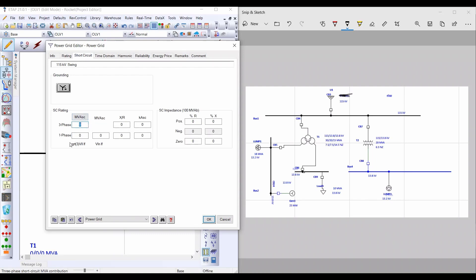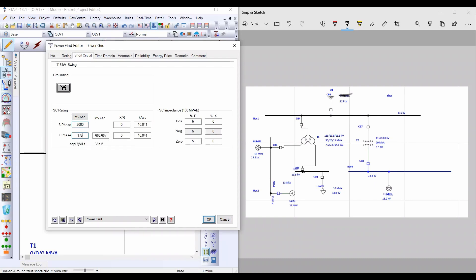Single-phase fault means line-to-ground fault. The value for three-phase fault is 2000 MVA short circuit, and for line-to-ground fault is 1750 MVA. The X/R ratio in case of three-phase equals 55, and in case of line-to-ground equals 48.